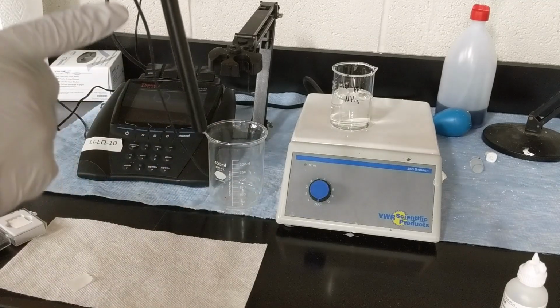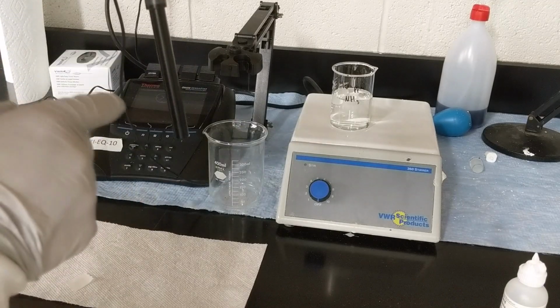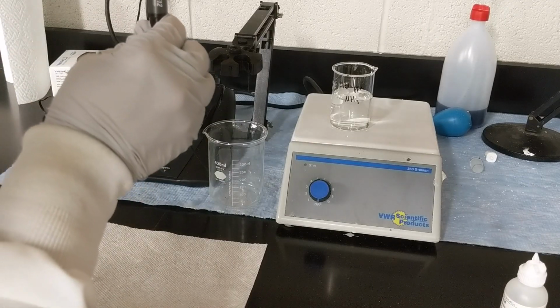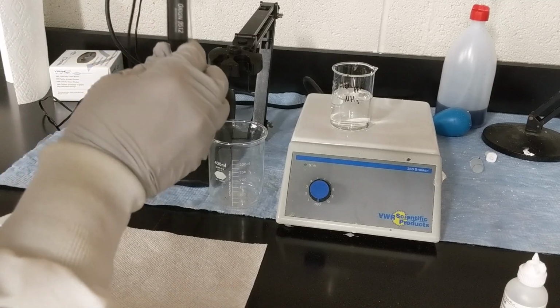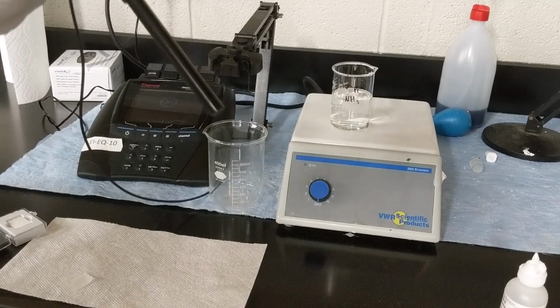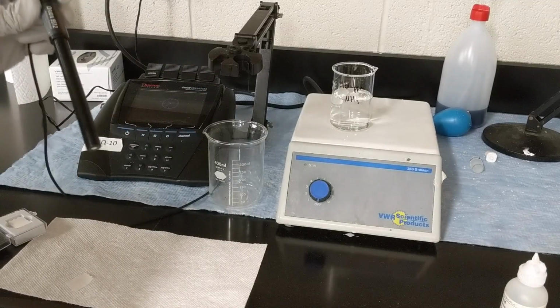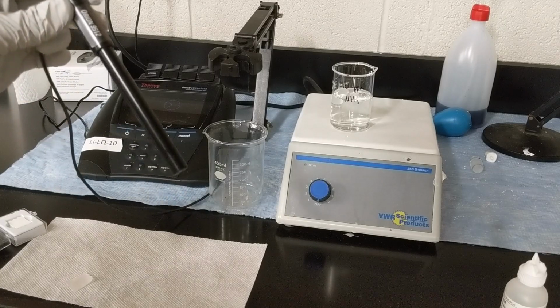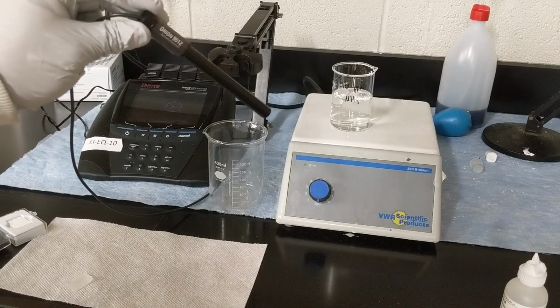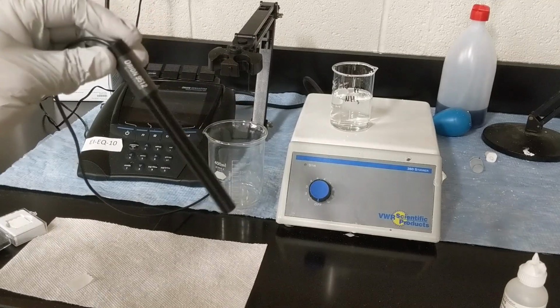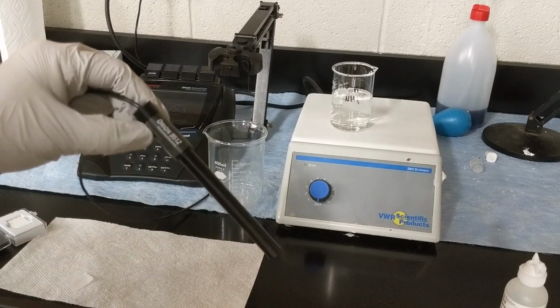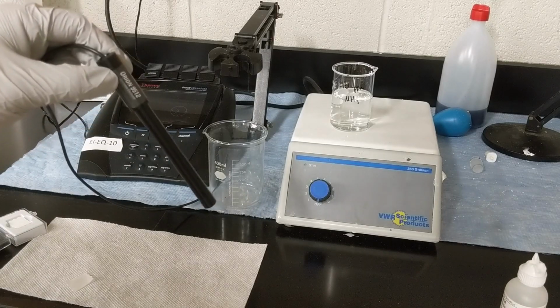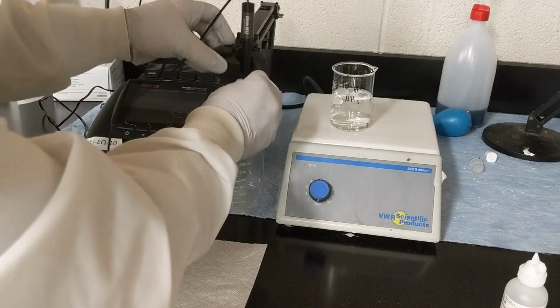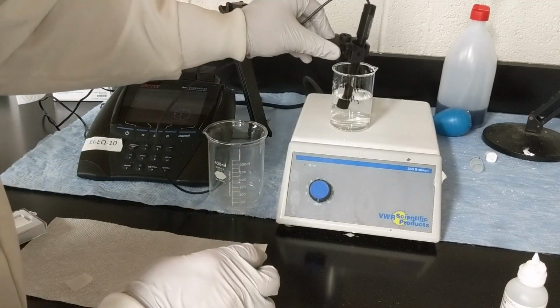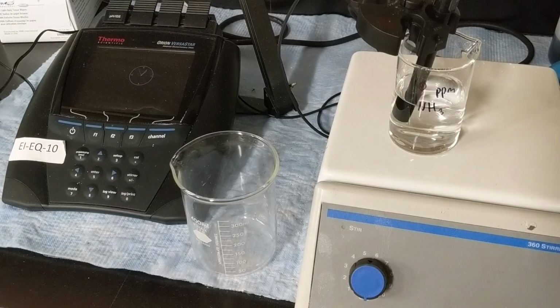And then to make sure that there is filling solution completely surrounding the electrode, you pull on this. You can feel a little bit of spring pushing back on it, and it's ready to go. So until I use it, I want to store it in this 10 part per million solution for at least 15 minutes, and it says ideally you want to do it for a couple of hours before running it. This has been sitting for a couple of hours, so it should be pretty well equilibrated at this point.